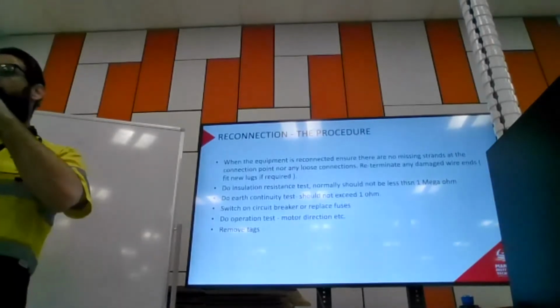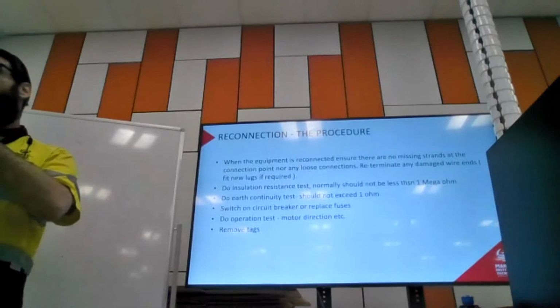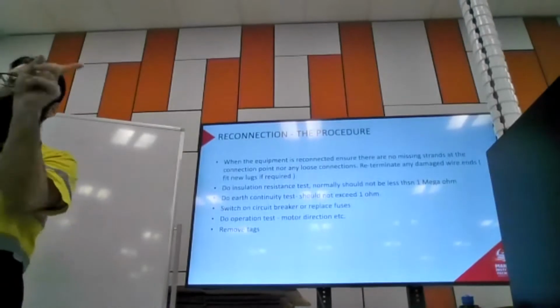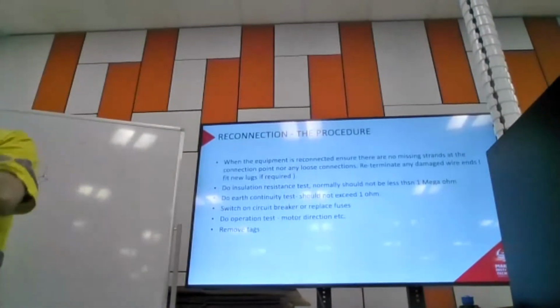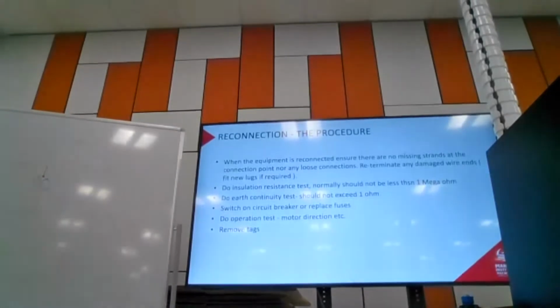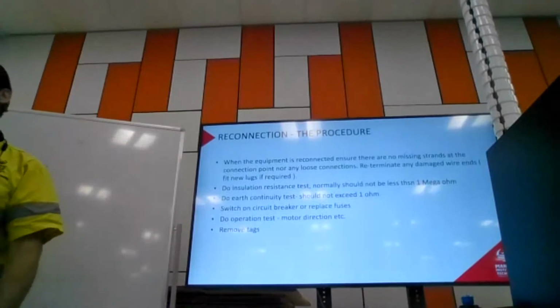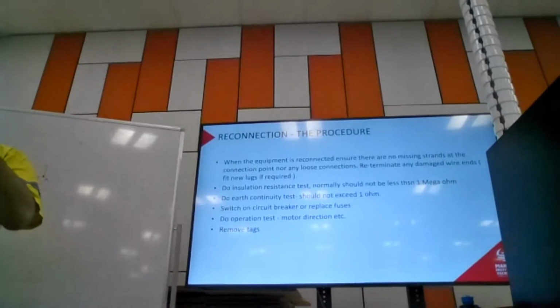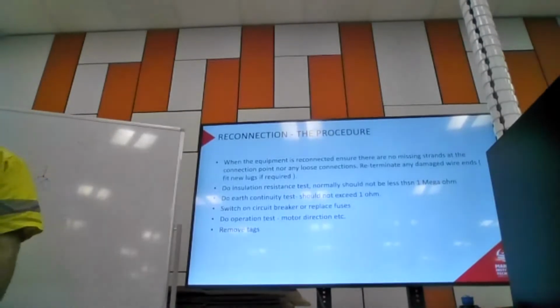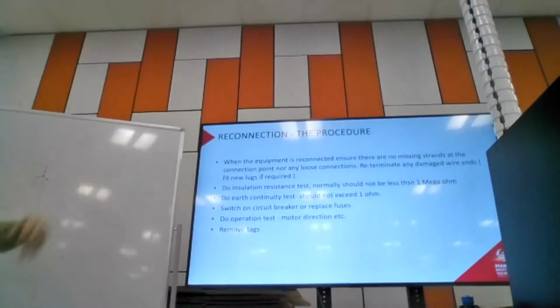So we should be making sure that no strands in our cable are broken off. None of them are sticking out of the connection. There's no exposed copper showing, all of that sort of stuff, which I'm certain that we've talked about before. If we've got any damaged wire ends, don't be lazy and sit there and go, oh, it'll be fine. Just restrip them, reconnect them, put new lugs on if you need to.